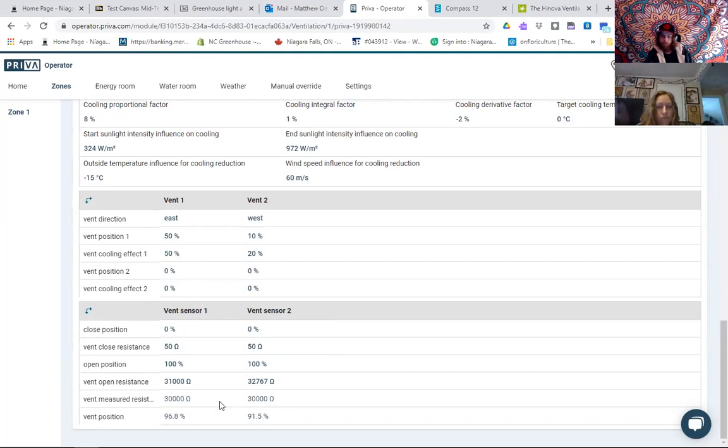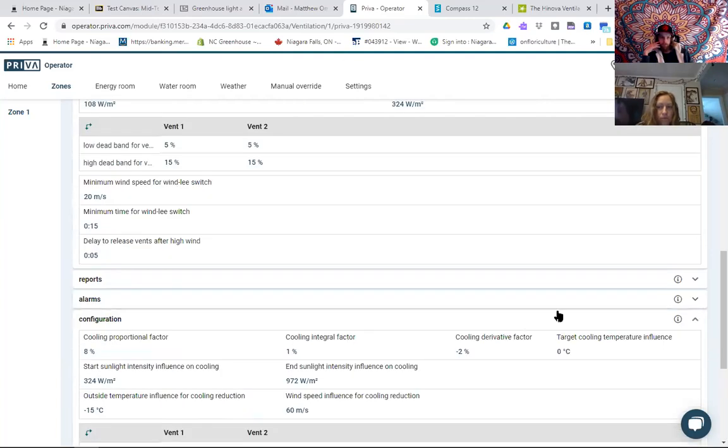And how you do that is you put the vents fully closed. Then you manually open them with a stopwatch. You time them to open, and you set the amount of time that it takes to open, right? So say if it takes 100 seconds for the vent to open, 10% cooling would be 10% open. The vents would open for 10 seconds, okay? So that's how we know that. Anyway, before we get into the weeds on that, any questions on vents? I know I went over that quickly.